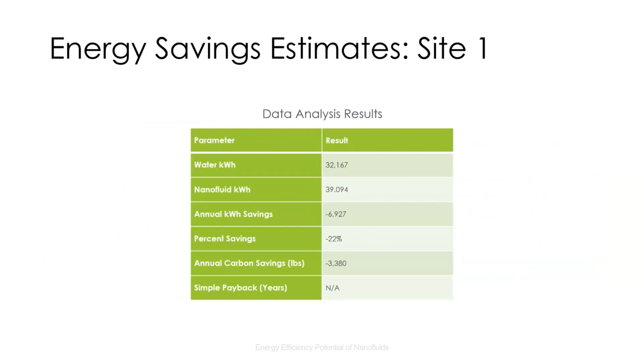So, as seen in the table here, the energy savings were estimated to be negative in this case. And we feel that a major contributing factor is that the data indicate that chiller loads were about just 1/4 of the equivalent full load hours that are stated for chillers in the Minnesota TRM, and even the data indicate that the chiller was only about 50% loaded during the warmest outdoor air condition period in the baseline in particular. We also found that the chiller appeared to have a chilled water reset sequence that further decreased the load at many conditions.